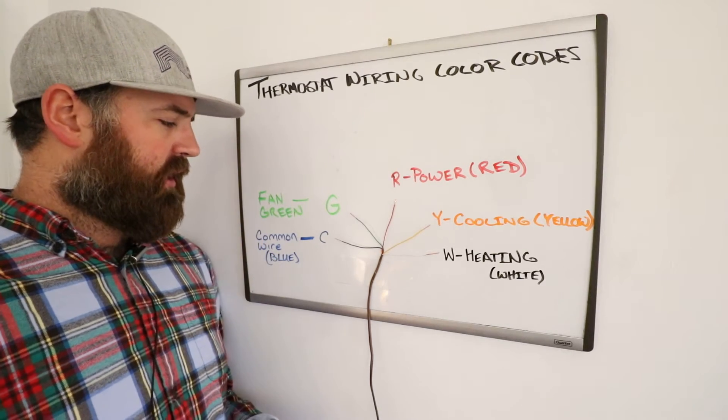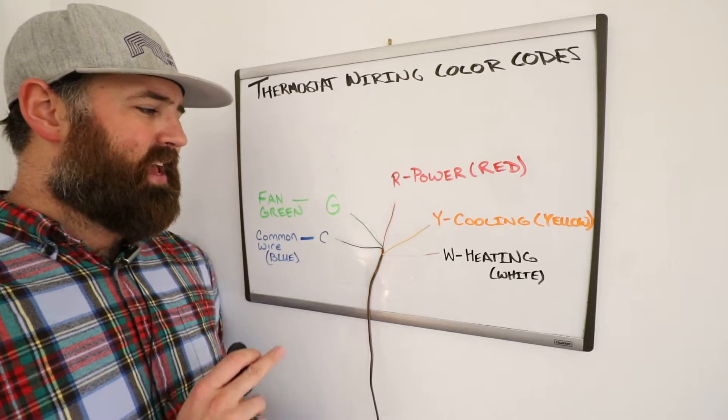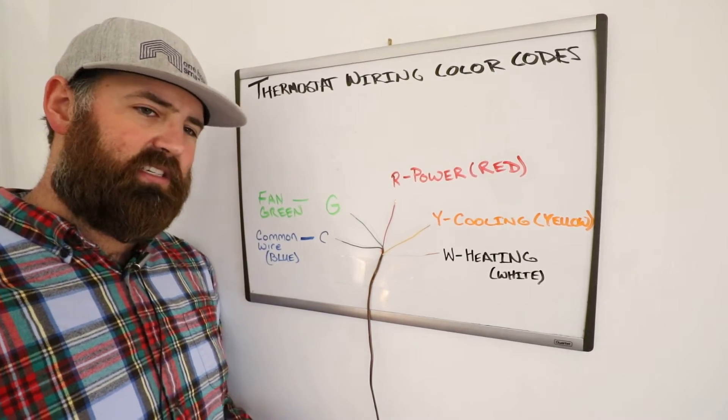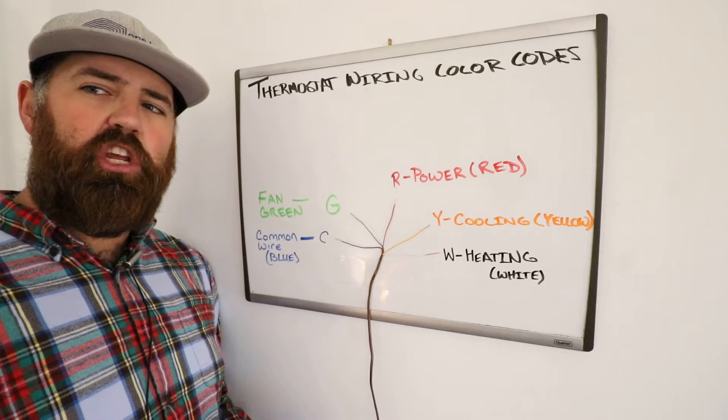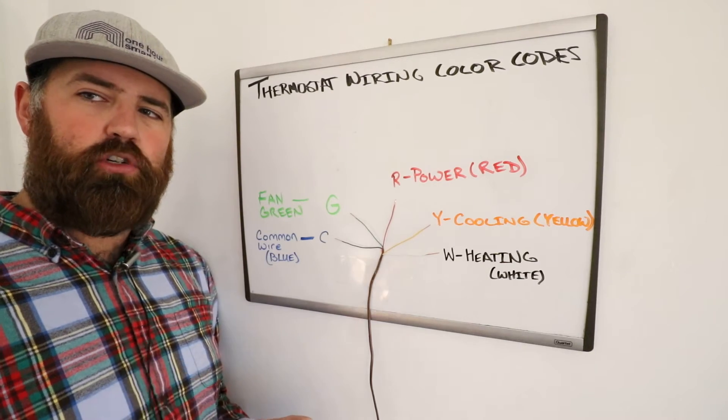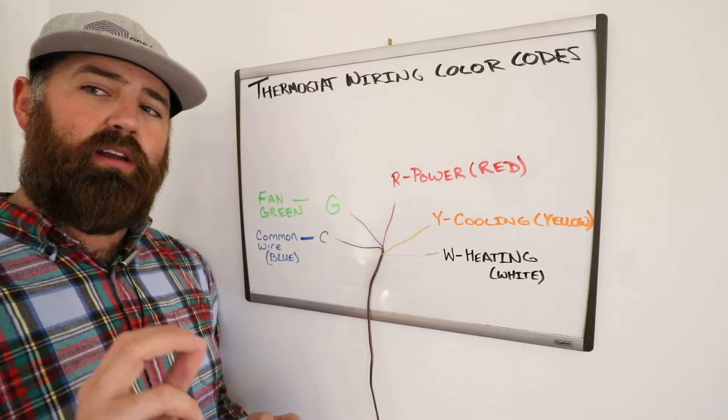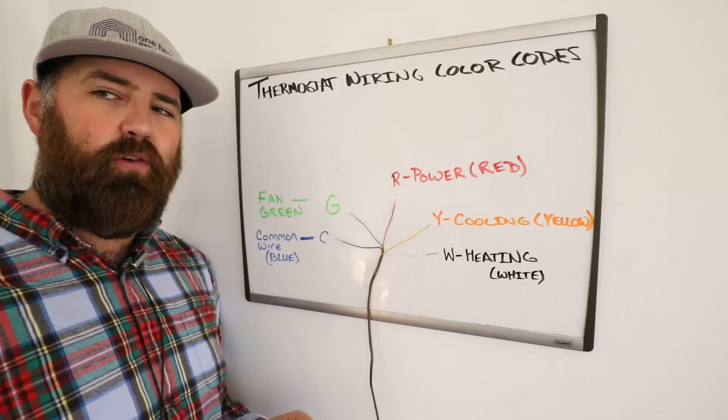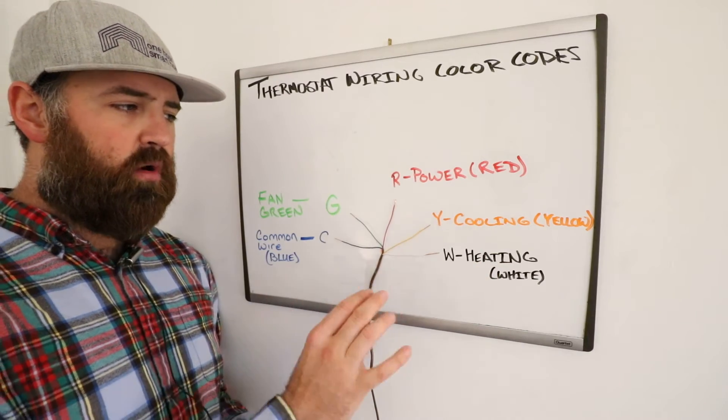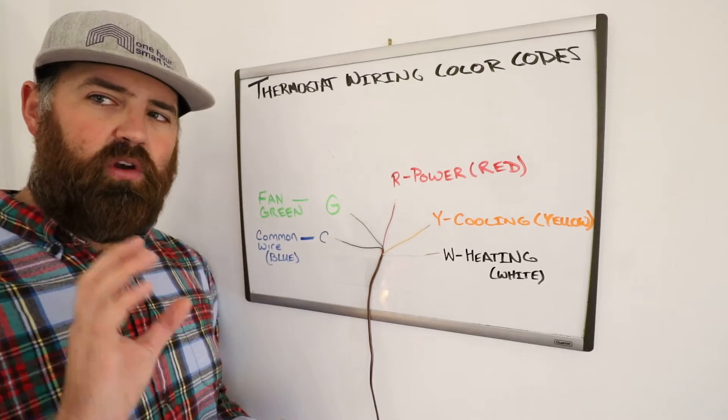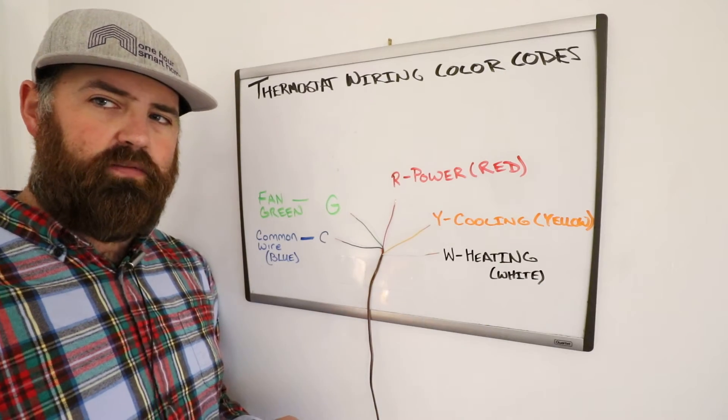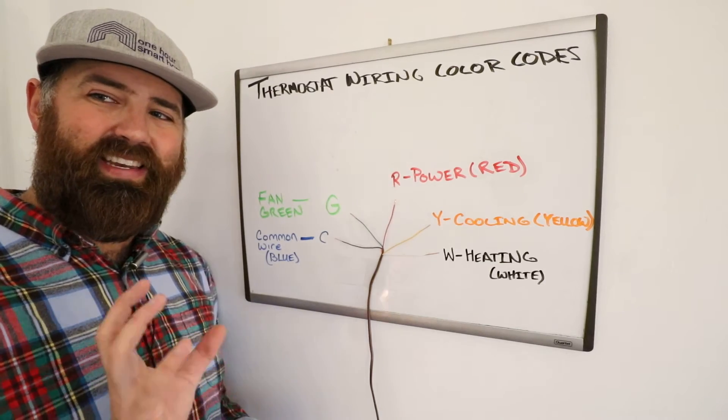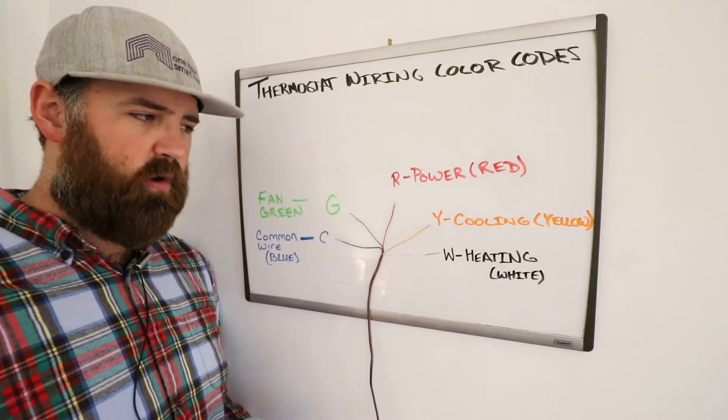The G-wire is the fan or green wire, and that actually isn't required for most HVAC systems, but most have it. What the G-wire does is allow you to control your fan to turn it on or off whenever you want, regardless if you have heating or cooling going. Normally, when you activate cooling or heating, it's going to automatically turn on your fan no matter what if you don't have a G-wire because your HVAC system knows that it needs to circulate air in order for it to work.